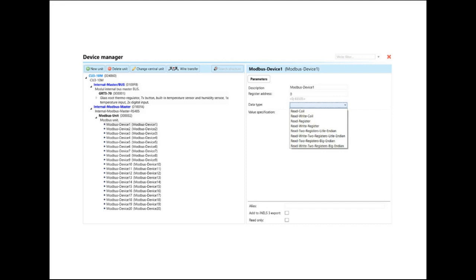So CU310, if you go to the IDM and add the parameters, Modbus master, you can add a normal iNELS bus, and you can add a GRT370 there. Then you can add a Modbus unit extra, and add a Modbus device, which is called Modbus unit. Then, by referring to the HVAC unit parameter table, you can set different addresses for different parameters.